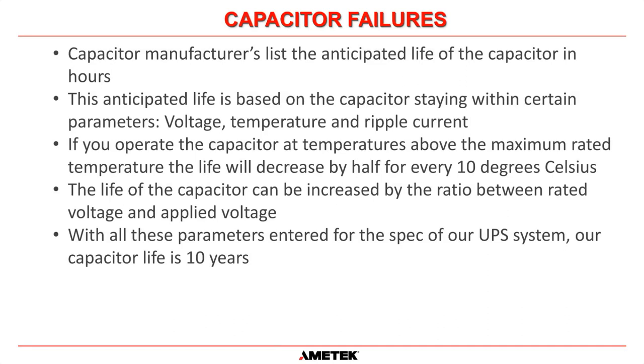Okay. Also, the life of the capacitor can be increased by the ratio between the rated voltage and the applied voltage. So if you're not applying as much voltage, your temperature is cooler, you will get additional life out of your capacitor. And with all these parameters entered in for the spec of our UPS system, the design engineers and the manufacturer of the capacitors all came together and said that our capacitor will last 10 years. So that's why we replace capacitors on a 10-year basis. It's because of all the parameters that the capacitor manufacturers give us, we extrapolate all of that data, and it says 10 years is the expected lifespan of our DC electrolytic capacitors. We don't just make it up.